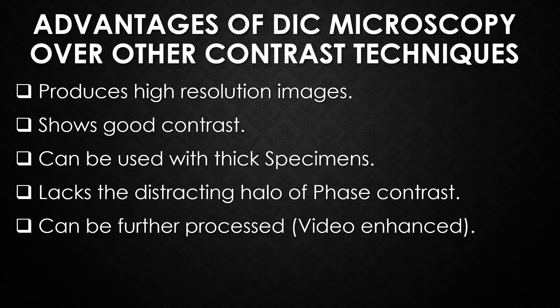An advantage of using DIC Microscopy over other contrast techniques such as phase contrast or oblique contrast is that in DIC, the full aperture of the microscope is used. For example, in phase contrast, the annulus of the condenser restricts the aperture, reducing the resolution of the image. And unlike phase contrast, DIC images are not disturbed by halo artifacts.